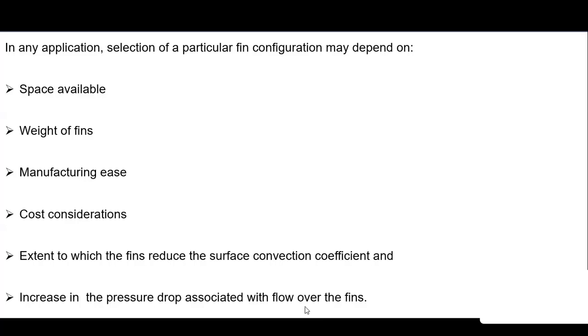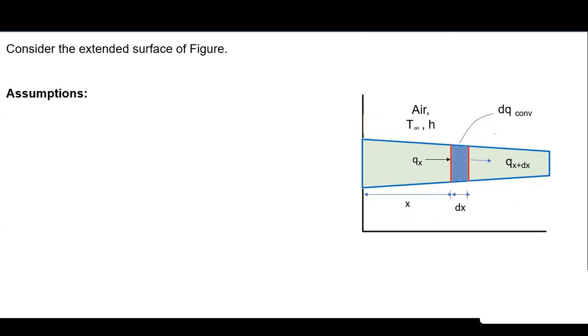Another important consideration is the increase in pressure drop associated with flow over fins. When multiple fins are provided on a surface, fluid movement — whether air or liquid — experiences a higher pressure drop. To overcome this, more pumping power is required. If the pressure drop is much higher, the increased operating cost may not justify the use of fins, even if the fins themselves are manufactured at low cost.